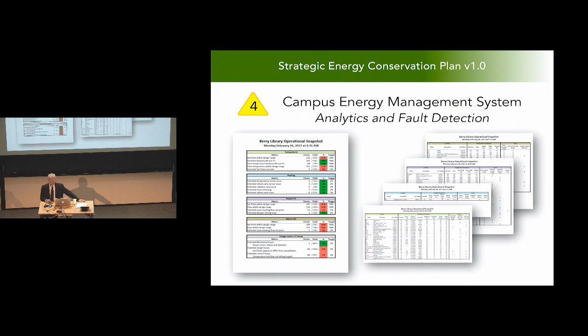Another great strategy we undertook early on was the elimination of absorption cooling for the campus. It was really the biggest overall opportunity we faced. Until 2008, the campus used the absorption cooling process, which uses steam to make chilled water. It's thermally extremely inefficient, but it was financially viable until about the beginning of our energy program. At that point, fuel oil became relatively higher priced, and electricity became relatively lower priced, and it flipped upside down and certainly did not make financial sense at that point.